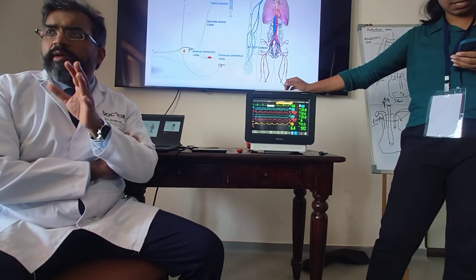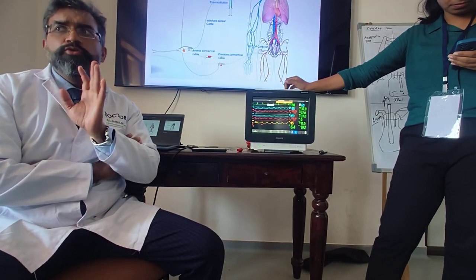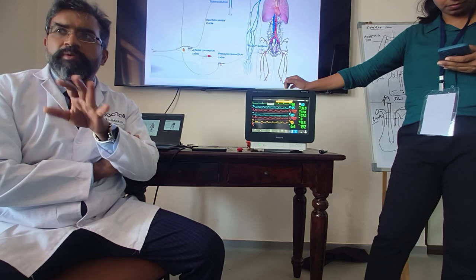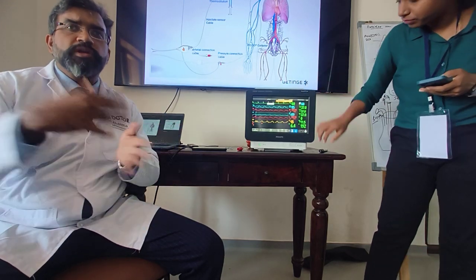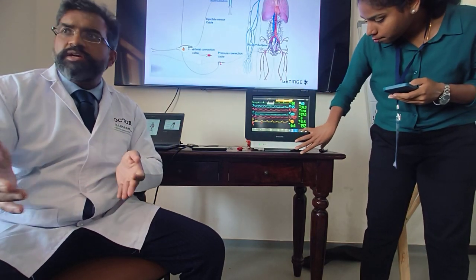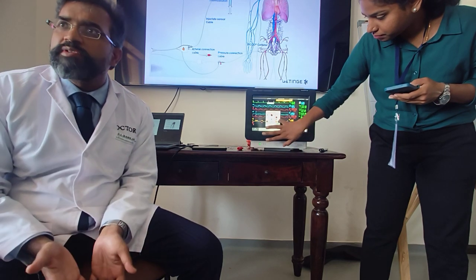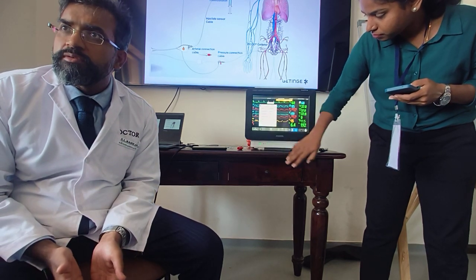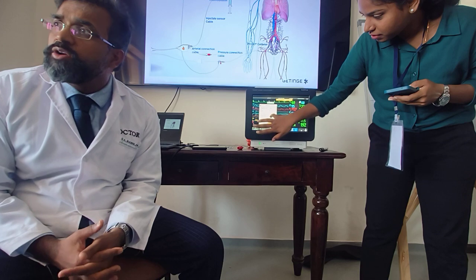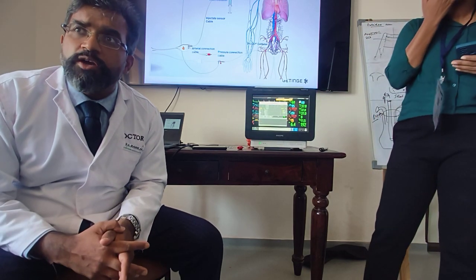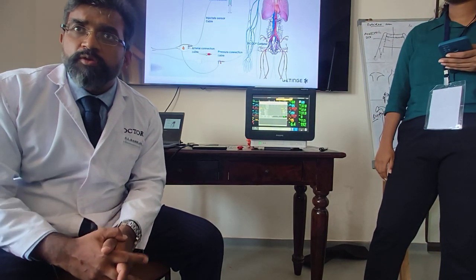So if you have an IBP on, you can still use it. We've used it. How do you use it? In IBP, switch off the IBP, do the thermodilution, see the cardiac output, but don't look at the continuous cardiac output. Why will it not work with IBP on? How does it monitor the continuous cardiac output? Looking at the pulse.